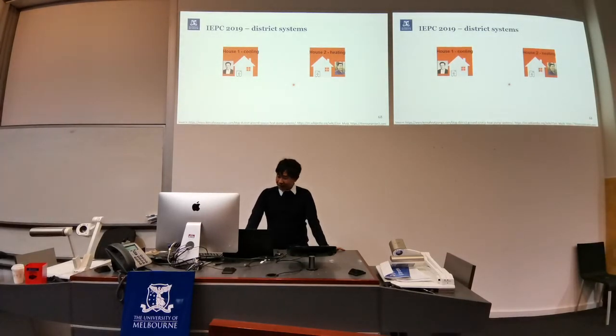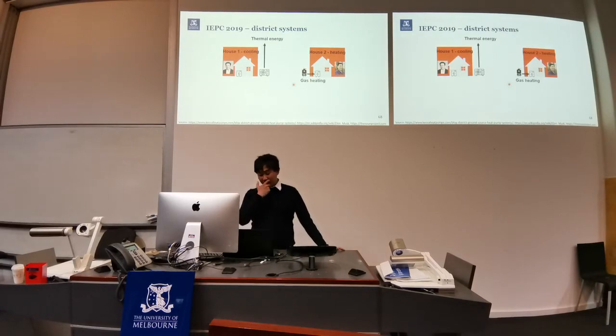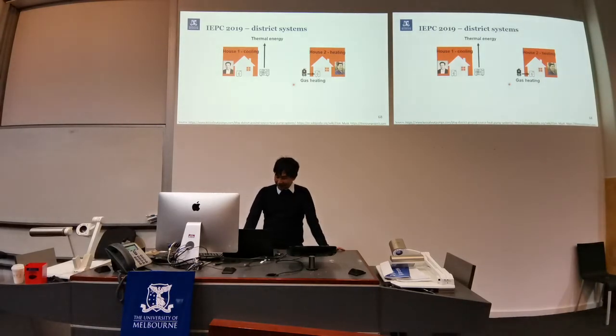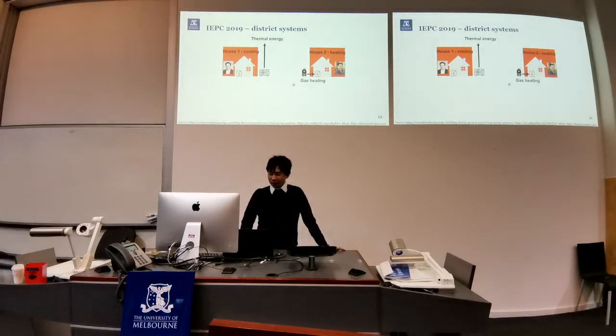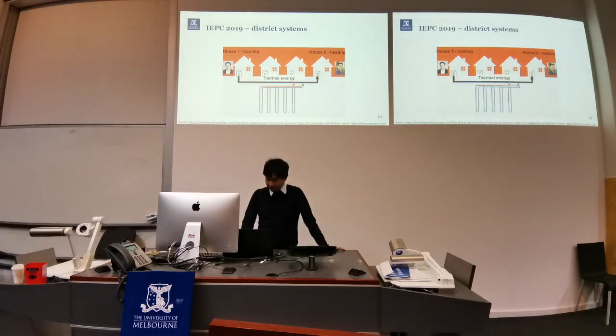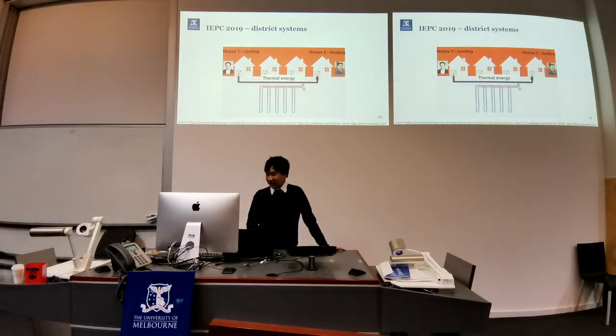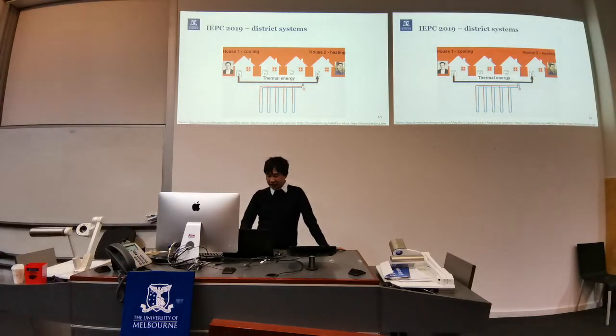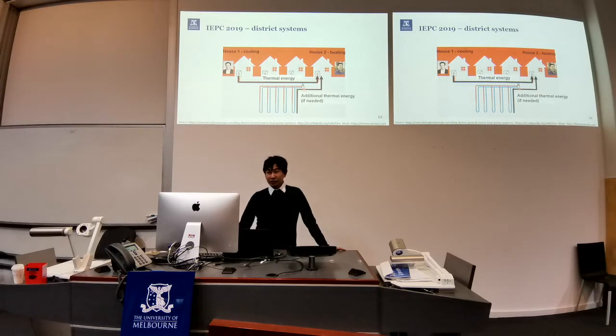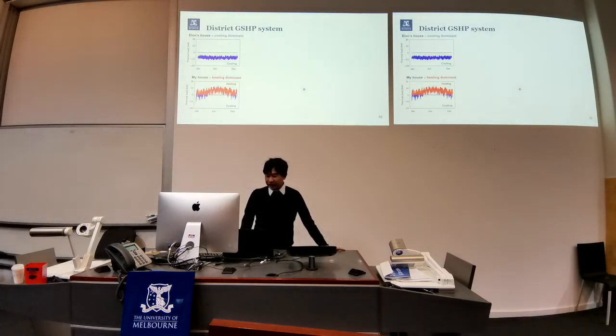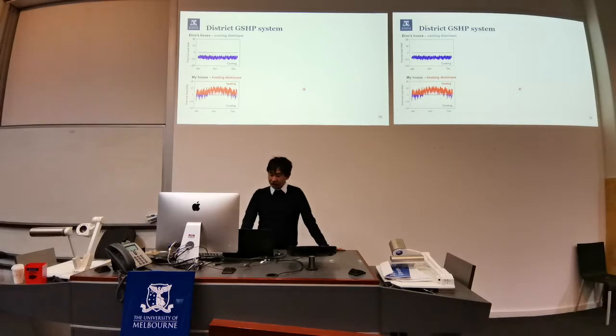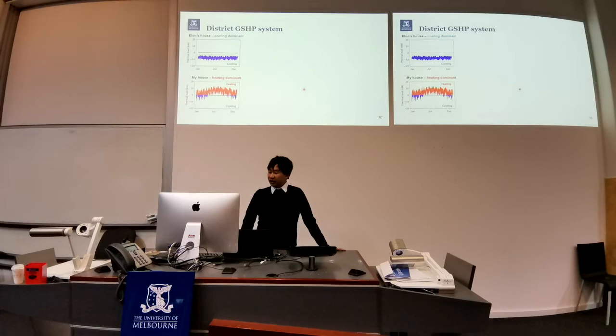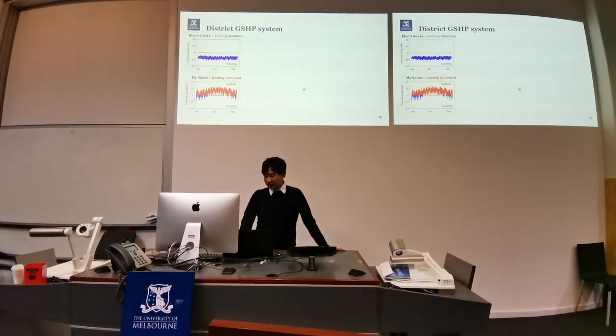In a conventional system, thermal energy from Elon's house is moved outside and essentially wasted to the air. Meanwhile, I use gas heating to provide heating for me next door. In a district system, we can move the thermal energy from Elon's house to my house instead. It's like Elon pays for my heating bill. If I need extra thermal energy, then I can use my heat pump to extract additional thermal energy from the ground. So in this research, I calculated 10 different thermal loads to represent possible thermal demands in different buildings. Two of those possible thermal loads are shown here, exemplified by my house and Elon's.